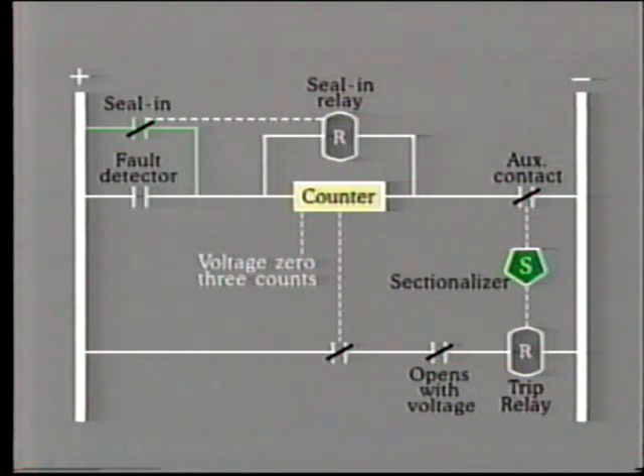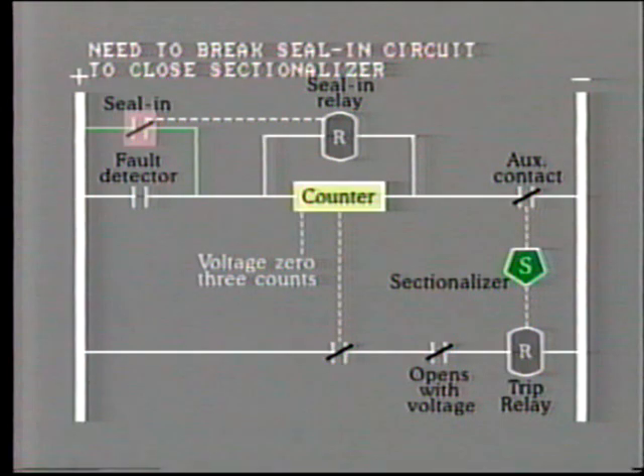One thing we have to remember here is that as soon as the sectionalizer is opened, we need to break the seal-in circuit. This is to allow us to close the sectionalizer again after the fault has been cleared. This is achieved by including an auxiliary contact which opens when the sectionalizer opens.